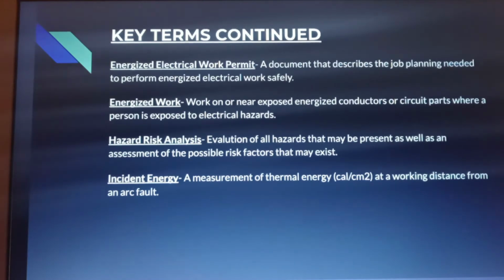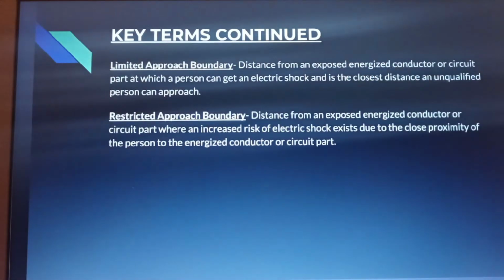And then incident energy is a measurement of thermal energy, in cal/cm², at a working distance from an arc fault. The last two terms that I think were important are limited approach boundary, which is the distance from an exposed energized circuit or circuit part at which a person can get an electrical shock, and is the closest distance an unqualified person can approach. Restricted approach boundary: the distance from an exposed energized conductor or circuit part where an increased risk of electrical shock exists due to the close proximity of the person to the energized conductor or circuit parts. And we will get into all of these terms more in depth here soon.